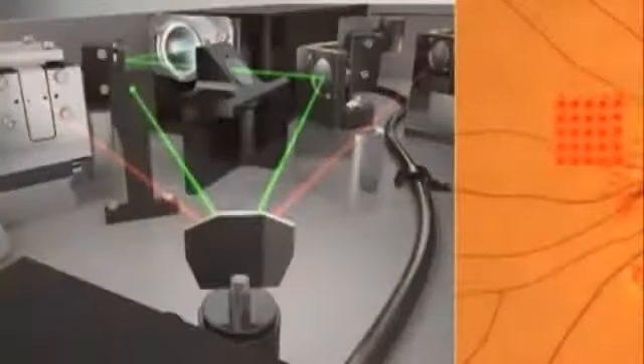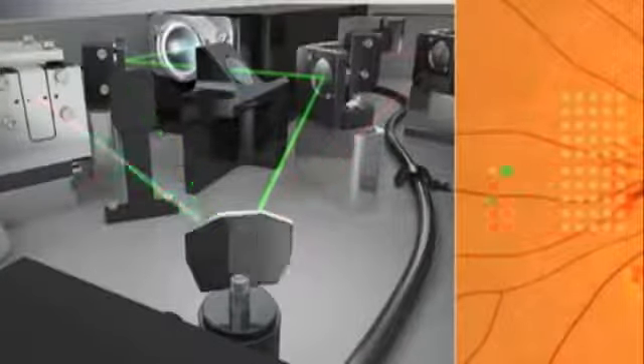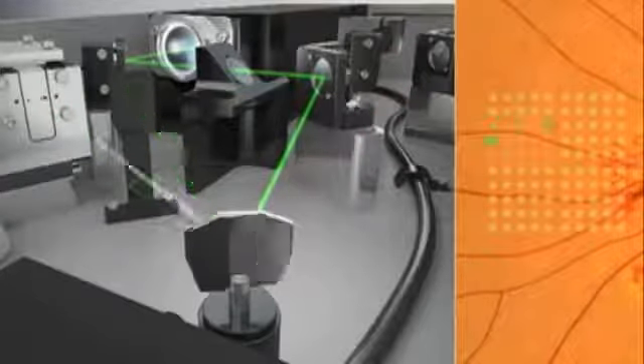The key to PASCAL is its proprietary advanced control system, which is fundamentally different from conventional lasers. PASCAL uses three high-speed computer-driven galvanometers to individually deliver each spot in the pattern, resulting in a 25-spot PRP pattern being delivered in approximately 500 milliseconds.